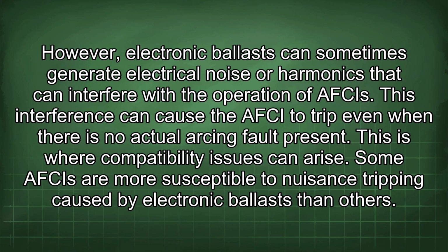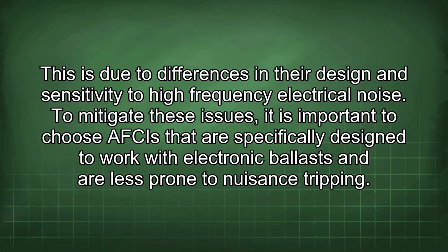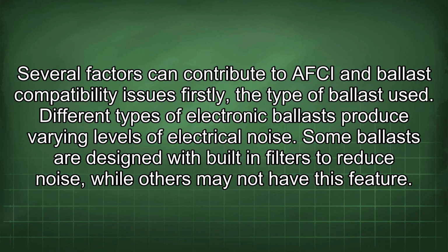Some AFCIs are more susceptible to nuisance tripping caused by electronic ballasts than others. This is due to differences in their design and sensitivity to high-frequency electrical noise. To mitigate these issues, it is important to choose AFCIs that are specifically designed to work with electronic ballasts and are less prone to nuisance tripping. Several factors can contribute to AFCI and ballast compatibility issues.